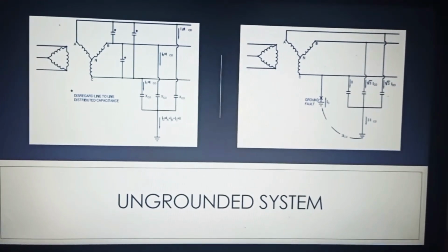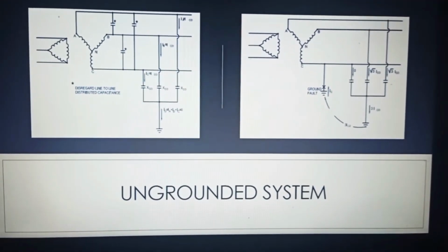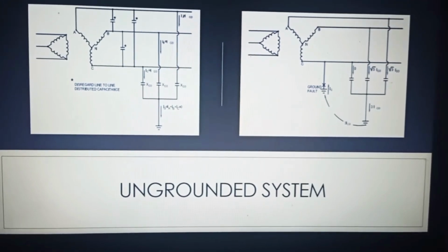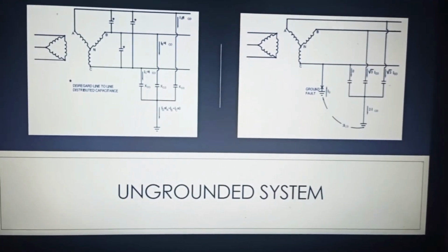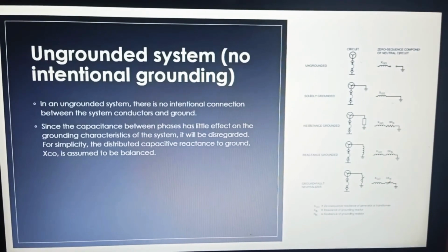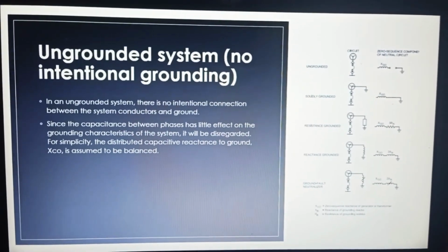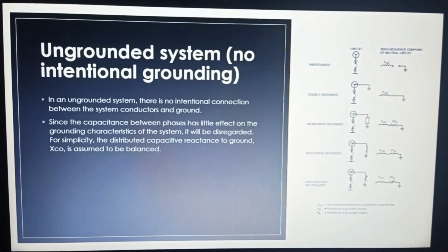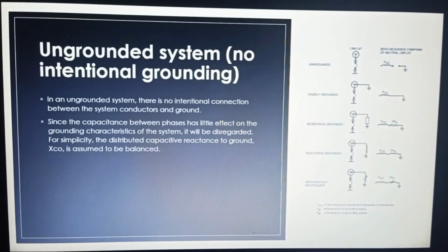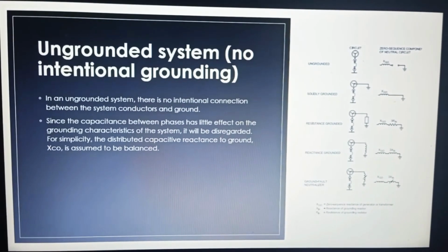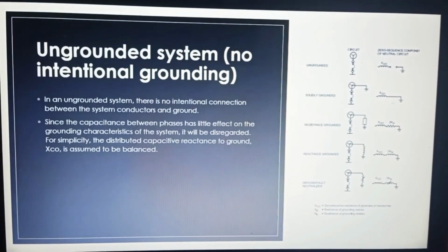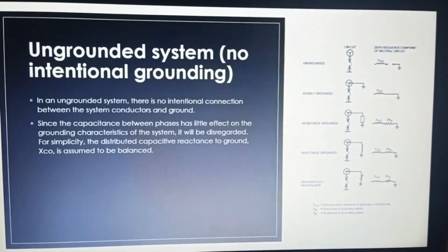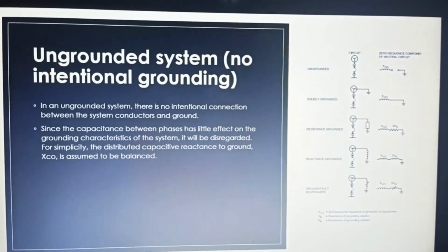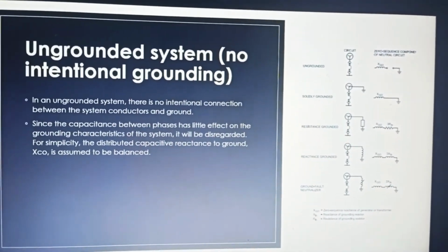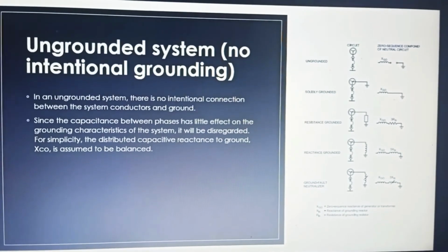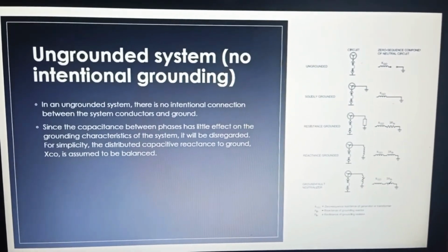The fault current flowing from the faulted conductor to ground leads the original line to neutral voltage by approximately 90 degrees. In an ungrounded system, it is possible for disruptive transient overvoltage to occur throughout the system during a restriking ground fault. This overvoltage can be several times normal in magnitude, resulting from a resonant condition being established between the inductive reactance of the system and the distributed capacitance to ground. This phenomenon is discussed in detail by Beeman.